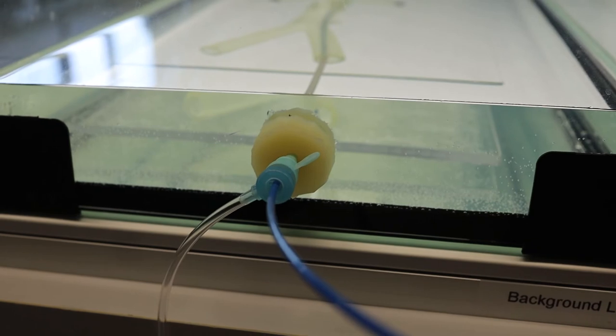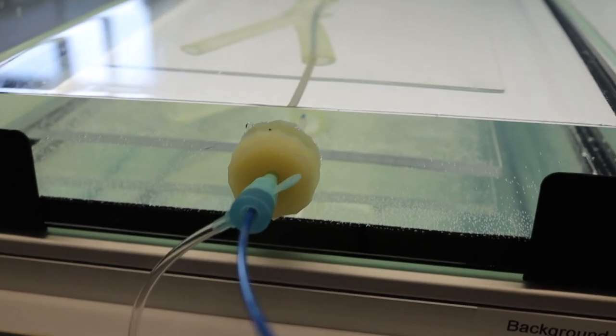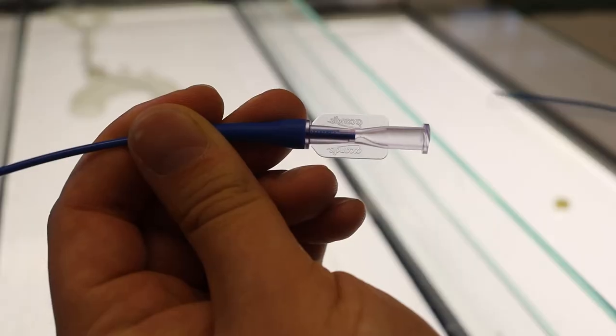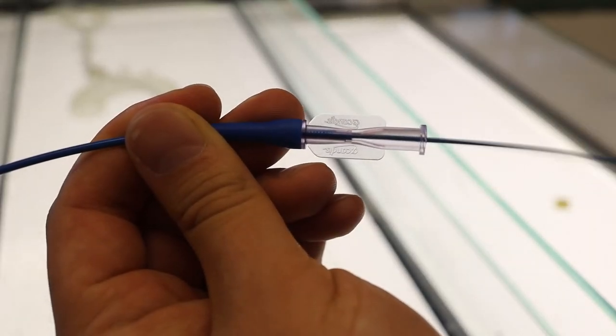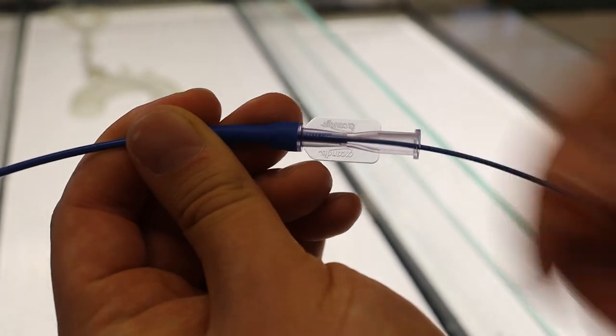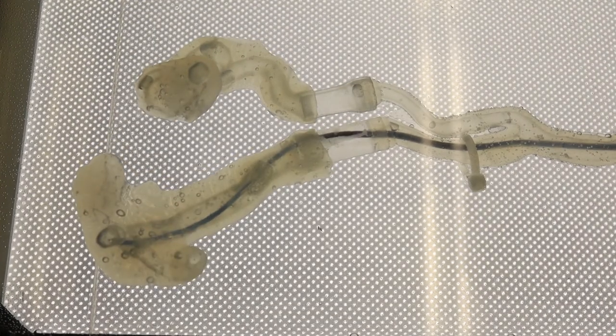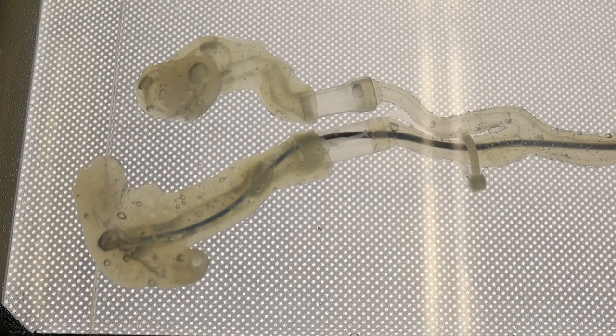Let's have a look at the artificial vessel model. A guide catheter is already set in place. The model starts at the arteria iliaca communis, follows the aorta up to the aortic arch, and continues to the indicated arteria carotis and the aneurysm models. Insert the microcatheter into the guide catheter. Guide the microcatheter up to the aneurysm, where you can release the implant by pushing the transport wire forward.